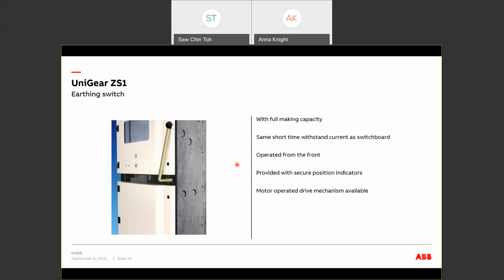The earth switch will be operated from the front using the handles that come together with the switchgear. We can also provide a motorized earthing switch for customers who want to switch the earthing switch remotely. The position of the earthing switch is indicated at the front of the cubicle, with a mechanical indicator linked to the circuit breaker mechanism.